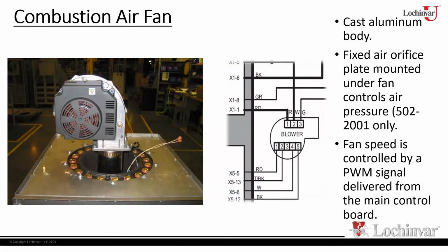Now, something else that you'll notice, and you'll see it mentioned here, a fixed air orifice plate for the 502 to 2 million ones only. And the reason for the plate, all right, for your models from 500 to 1.3 million BTUs, there is a fan. For, I believe, the 1.5 to 2 million, there is a fan. So you've got one fan that covers quite a bit of range, right? So say as an example for the 500 to the 1.3 million BTU models, one fan. That fan has to be able to go up to 1.3, but then be able to go down to 500 plus whatever it can modulate down to, all right? So I've got a very large fan here. It can't go down that low. I can't turn it down low enough to allow it to work the way I need it to work. So in this case, we're going to use a restrictor plate, if you will, that goes on the discharge of the blower to basically control or restrict how much air goes into the burner for the smaller models.